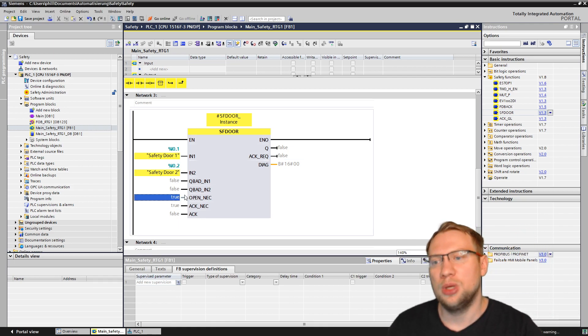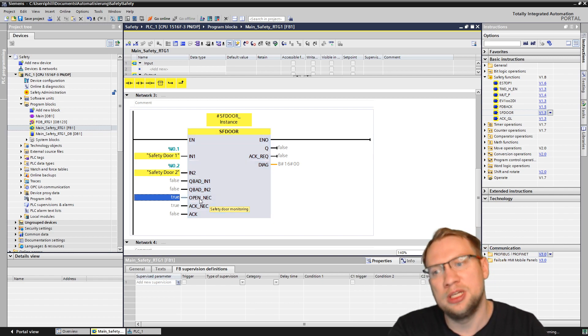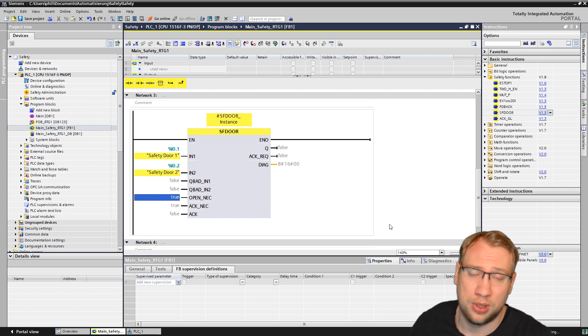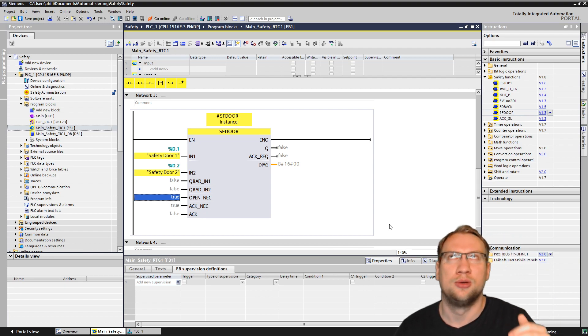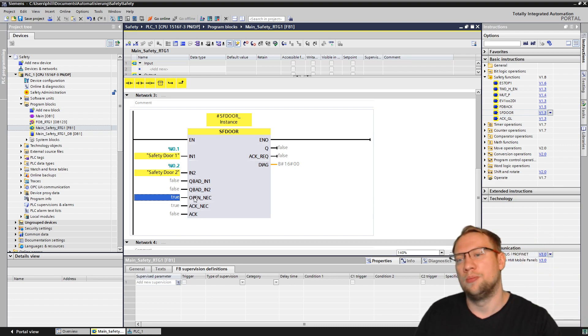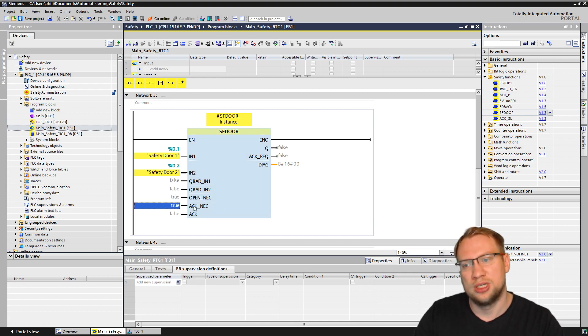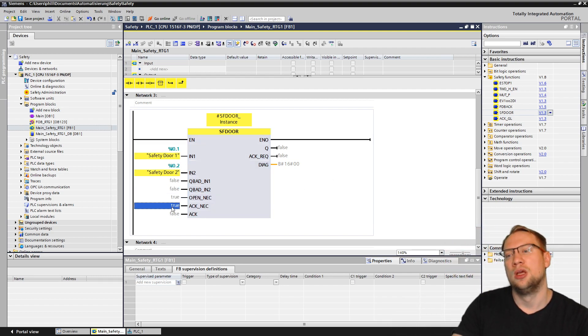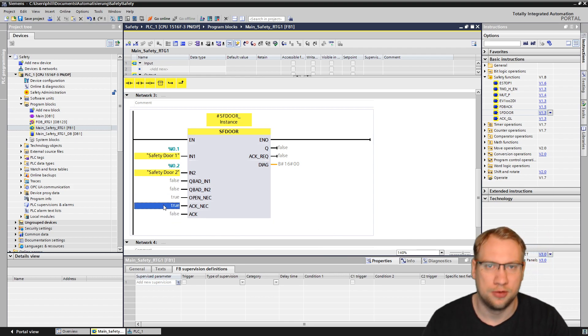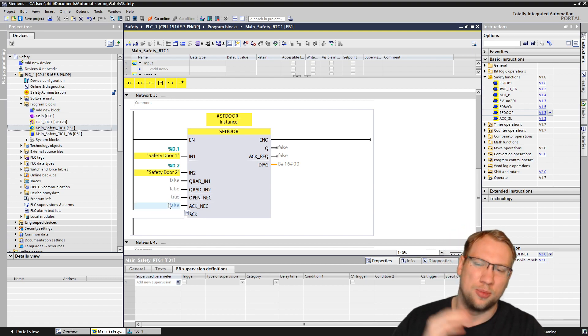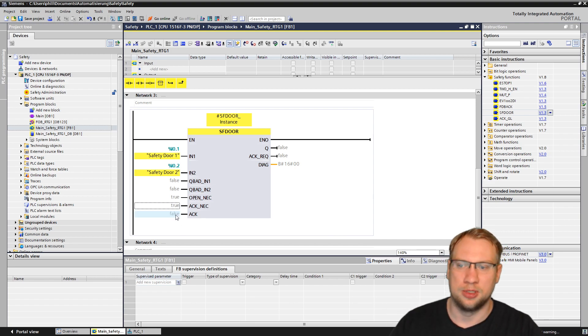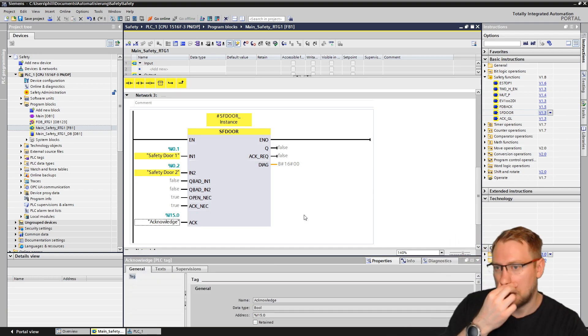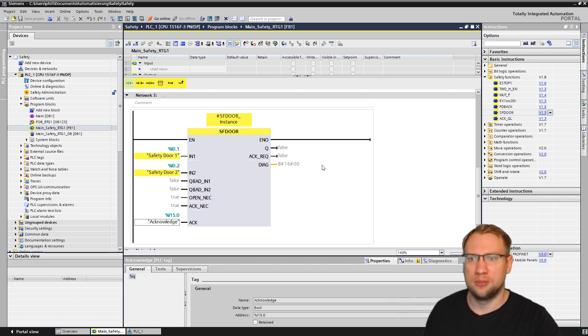Then we have OPEN_NECESSARY — that means we need a zero signal on both inputs at the beginning to be able to use the block, so the block needs to detect the door was open before it can register it as closed. That's set to true, which makes total sense. Then we have ACKNOWLEDGE_NECESSARY — if there is an error, for example if the two sensors have different states when they shouldn't, we have to activate the acknowledge. It's always recommended to leave it on; if you turn this to false you're not meeting the standard anymore. And the last input is of course the acknowledge input, the same as we had with the e-stop in the last video.